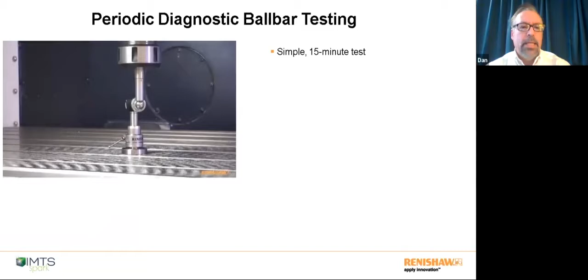This benchmarks the machine capability. So you've tuned the machine, it's installed by the OEM or you've installed it yourself and calibrated it. This benchmarks it and gives you a number that tells you the performance and positioning accuracy of that machine volumetrically.